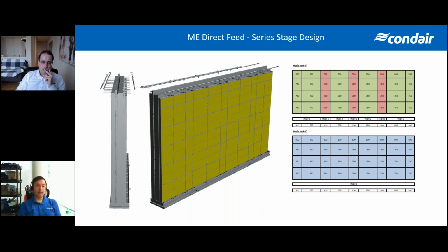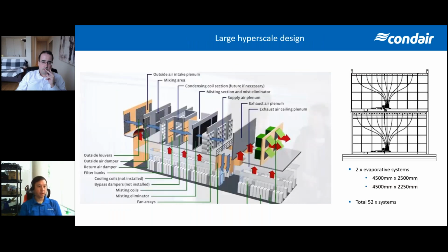And then stage 3, of course, would be the 4-inch bank and the 6-inch bank on at the same time. We took that 1 step further and actually optimized the staging on the 4-inch bank just to give them a bit more modulation on the low end. So you can see we lined up the individual columns with the fan arrays that they had. So we could turn on stage 1 as the smaller columns on the 4-inch bank, and then stage 2 would be the larger columns, just to give a bit more controllability on the low end. But in terms of air stratification with that type of setup, on this fairly wide system, we had less than a 1 to 2 degree temperature difference from the top corner to the bottom corner on the opposite side. So very effective in terms of eliminating stratification in the airstream.